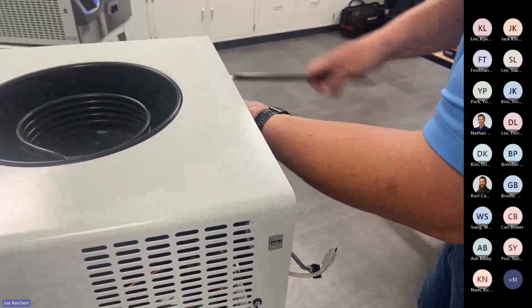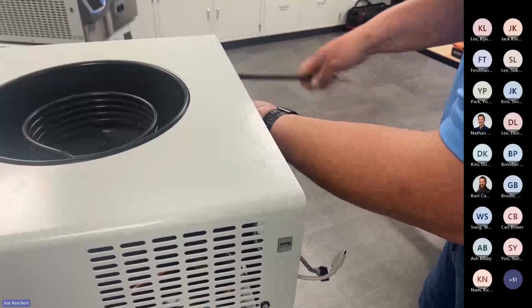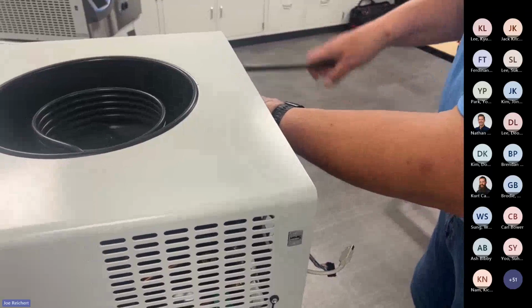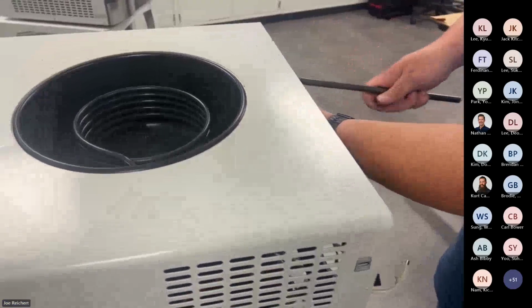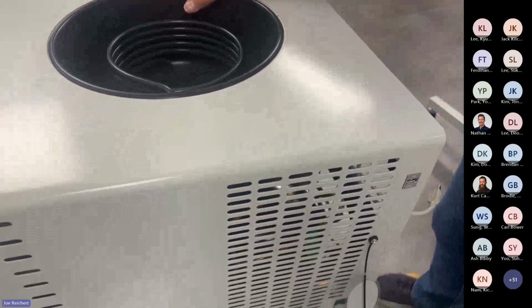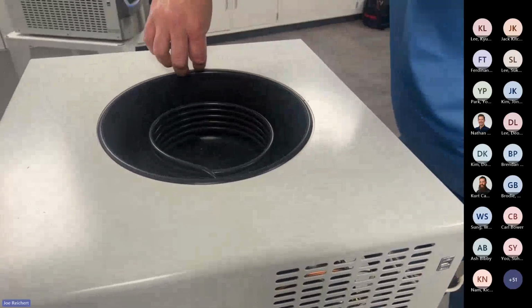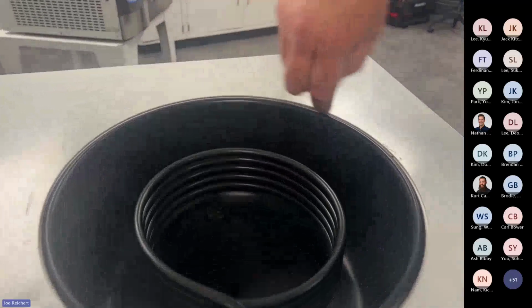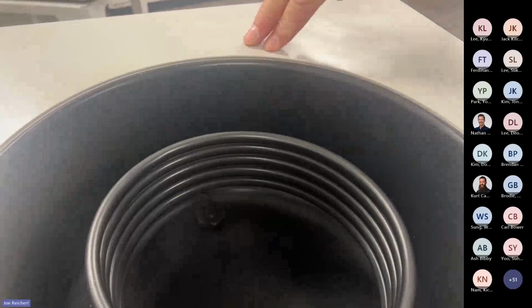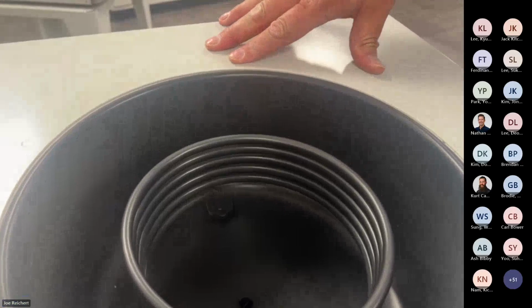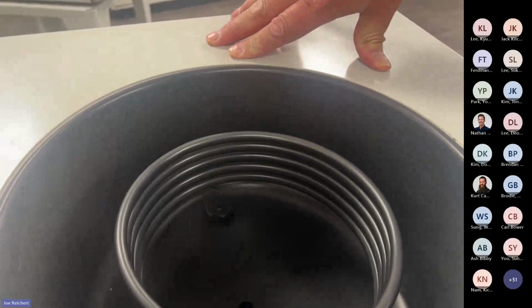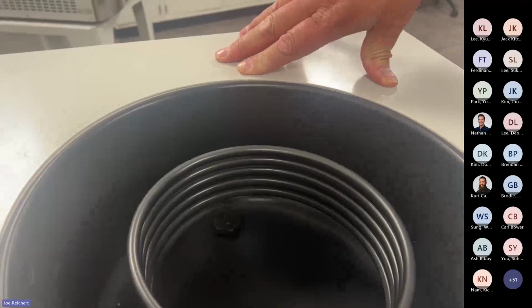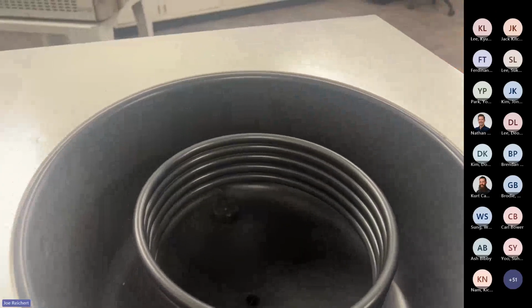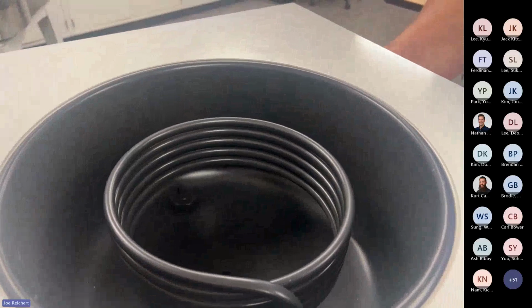Now, another possible scenario for a vacuum leak I've seen on some older systems, or maybe you have a stop ring tray jar on a console, something that's heavy, and somebody landed something on top of the rim of the chamber. If you could see right here, there's a gap between the chamber and the upper wrapper. See how I can push this down? This rim has to be up above the height of this wrapper for our gaskets to seal from our chambers, from our small tray dryers, things like that, have to seal to this edge. What can happen is these studs underneath are welded on the bottom.